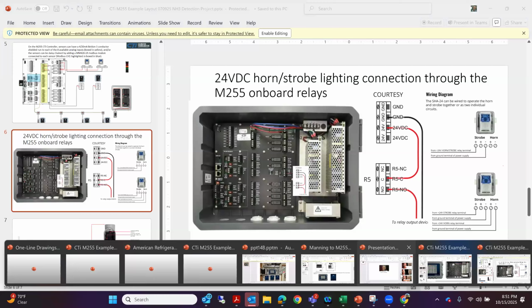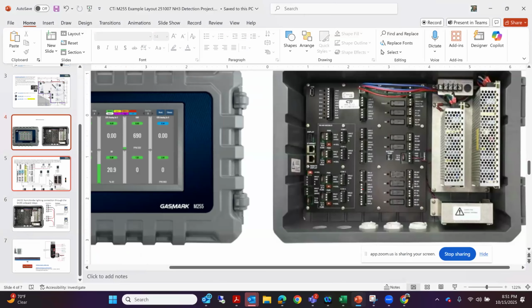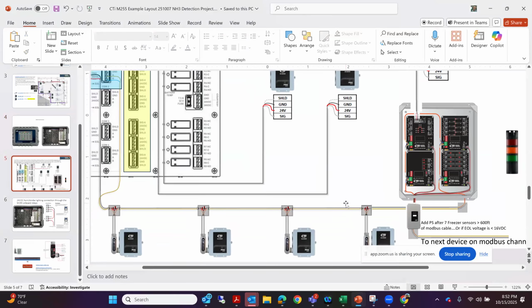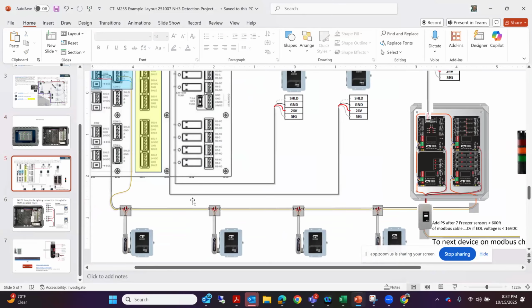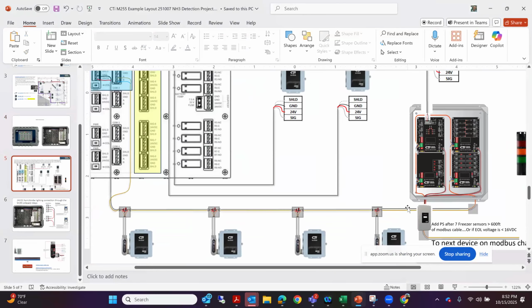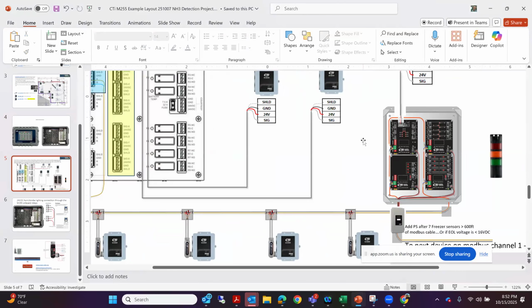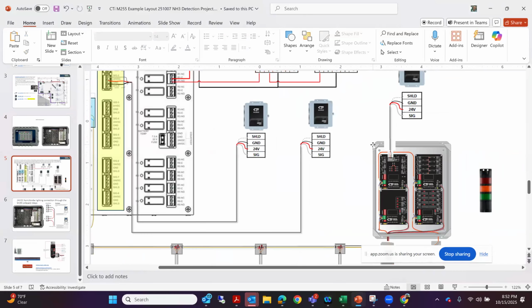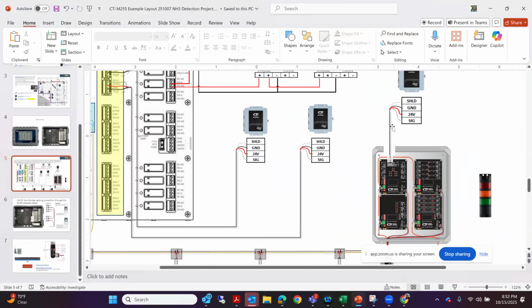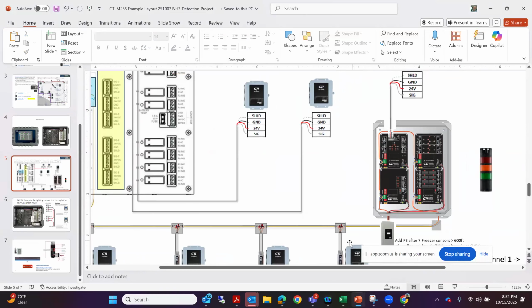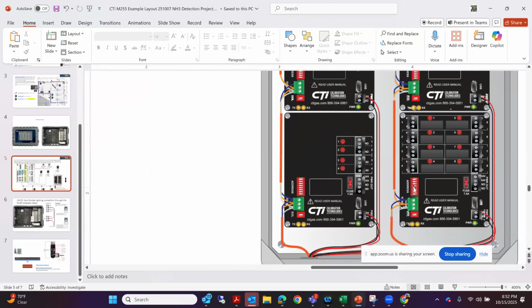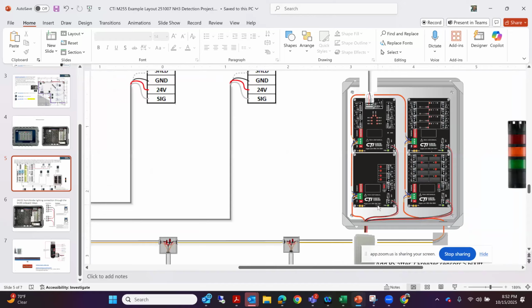One of the things we did do is add these remote relay boards out there. Anywhere along the way, like we were talking, if you need to add some stack lighting or horn strobe assemblies, or if you're picking up another standalone system along the way, you just add these analog input boards, or an analog output board feeding the PLC, or relay outputs if you want to put in a new zone of lighting. It's a lot easier to just daisy chain in these IO boards. Here's a discrete IO board, and they all have that same dip switch. You address them the same way, and whichever one is the last one at the end of the line.